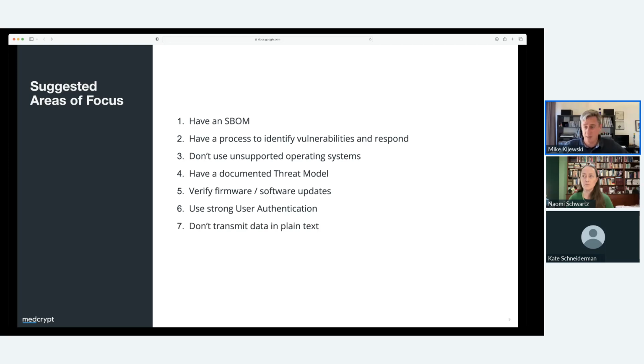Don't transmit data in plain text where you don't absolutely have to. Again, the issue here can sometimes be less about the data privacy. In other words, saying, oh, we're not sending a social security number, so we can send it in plain text. The concern tends to be more around data integrity. If the data you're sending in plain text says to deliver 800 units of radiation and somebody changes it to be 1800 units of radiation, that's a big problem.